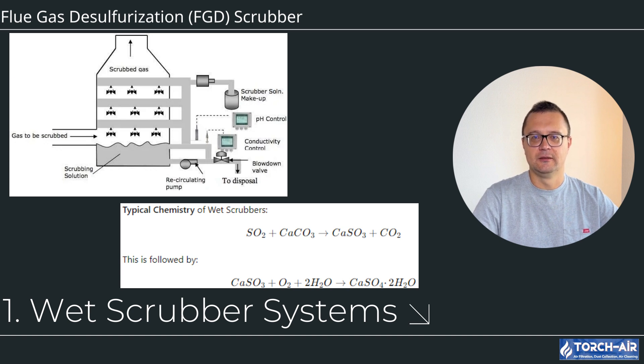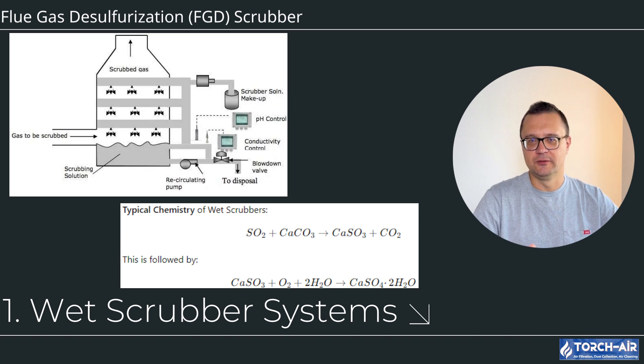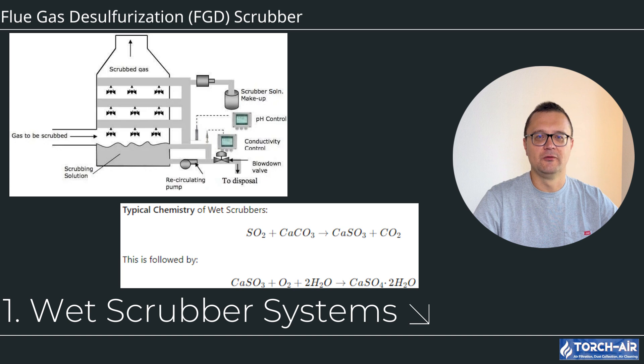In the reaction tanks, the reaction between SO2 and the alkaline slurry forms calcium sulfite (CaSO3), which can be further oxidized to form gypsum (CaSO4·2H2O), a byproduct that can be sold for use in construction materials. Mist eliminators help remove any entrained liquid droplets before the cleaned gas exits the system. The cleaned flue gas, now free from most of its sulfur dioxide, exits through the exhaust stack. Typical chemistry of wet scrubbers is shown on screen.